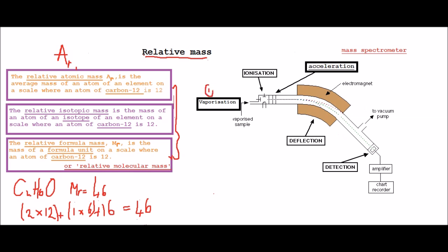This is stage 1 and it's called vaporization. Basically, a sample is put into the machine and it is turned into a gas, or we could say it has been vaporized using an electrical heater. So this is this stage here.